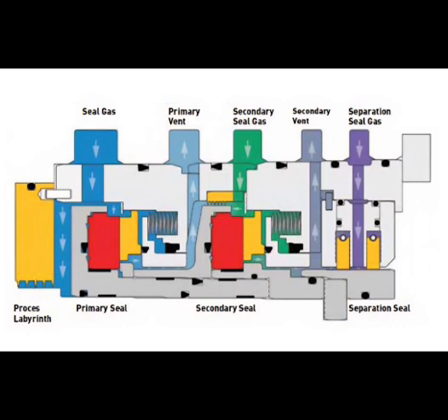Seal gas flows across the primary seal, inboard stage, of the dry gas seal out towards the primary vent, and across the inboard process labyrinth, back into the process. Seal gas prevents dirty, unfiltered process gas from entering the dry gas seal. This gas must be cleaned and conditioned so as to be completely dry and free of particulate contamination. The conditioning is usually accomplished via the addition of filters and a gas conditioning unit, such as separators, boosters, and heaters.